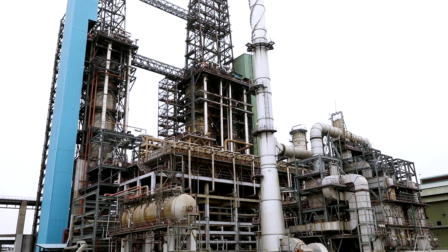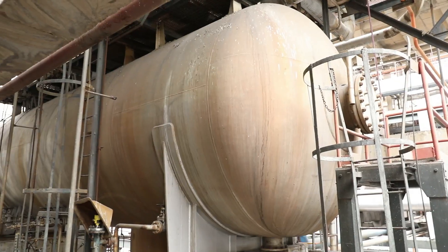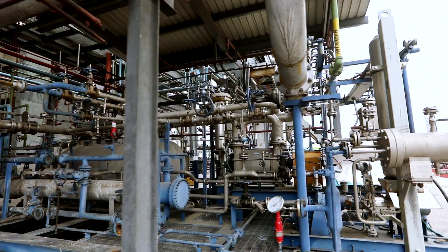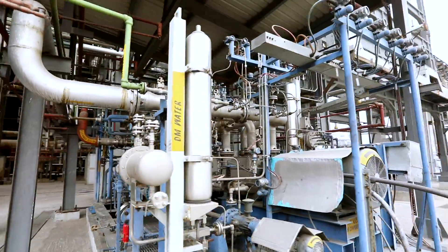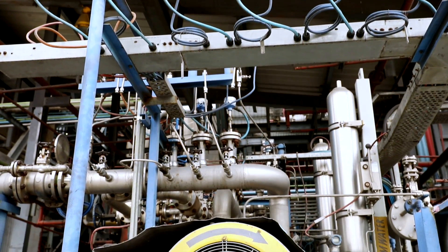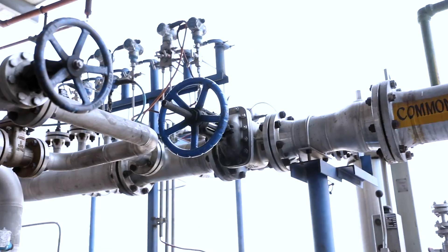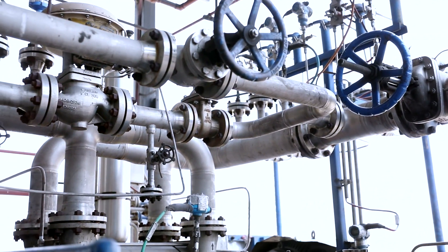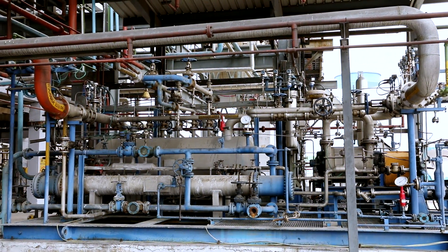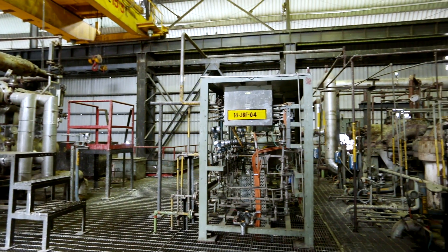With the intent of recycling the vent gas from the blow-down overhead receiver to the fractionator overhead receiver, the water ring compressor was commissioned. However, the water ring compressor was functional for only six hours in every 24 hours. It was therefore proposed to utilize the water ring compressor for flare gas recovery. The innovative FGRS uses the water ring compressor to recover the flare gas and sends it to the DCU wet gas compressor suction.